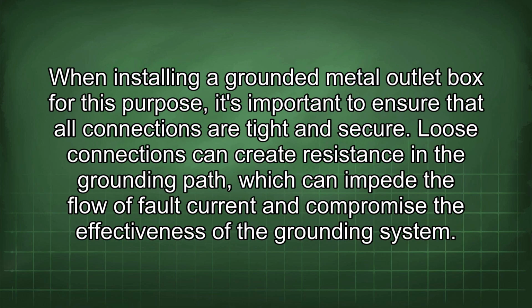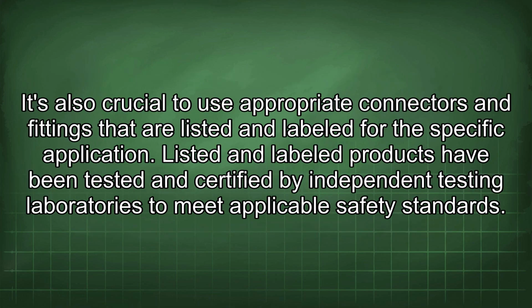When installing a grounded metal outlet box for this purpose, it's important to ensure that all connections are tight and secure. Loose connections can create resistance in the grounding path, which can impede the flow of fault current and compromise the effectiveness of the grounding system. It's also crucial to use appropriate connectors and fittings that are listed and labeled for the specific application. Listed and labeled products have been tested and certified by independent testing laboratories to meet applicable safety standards.